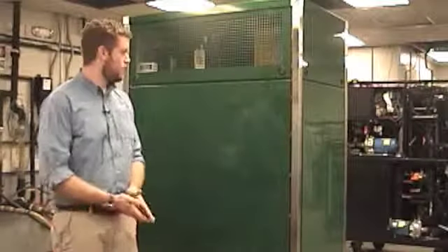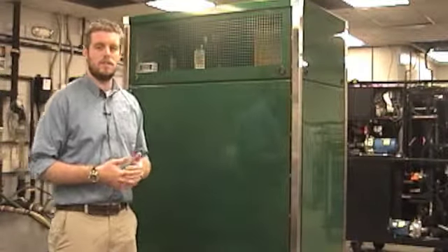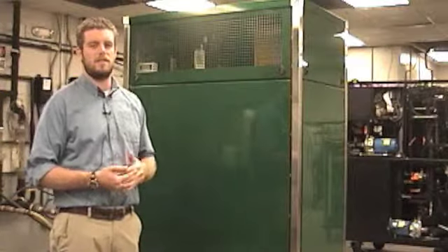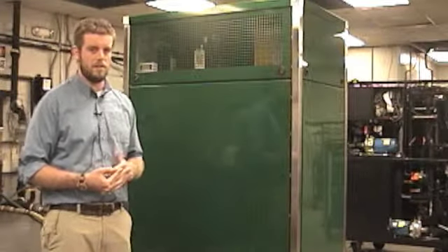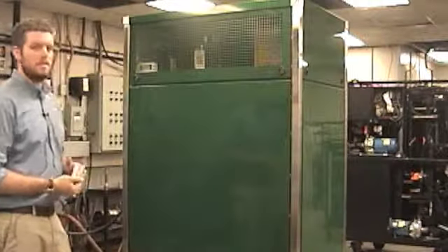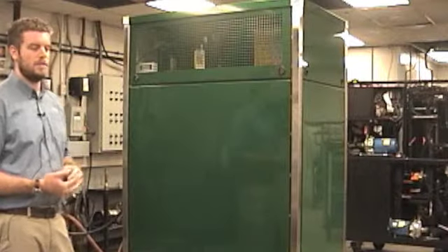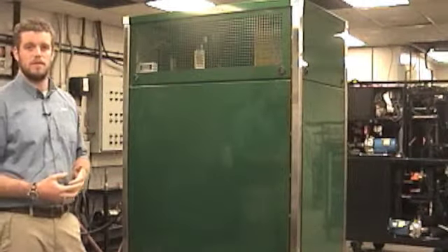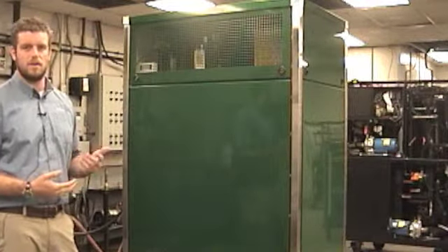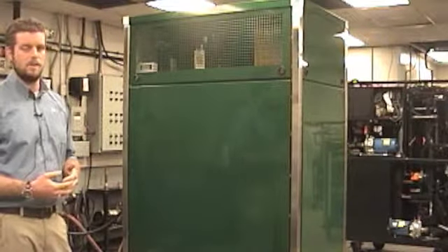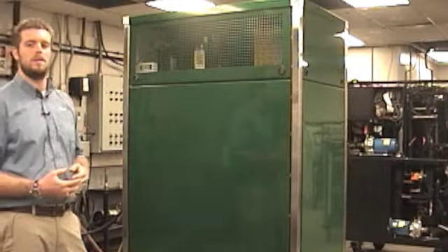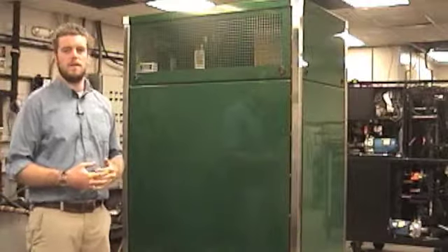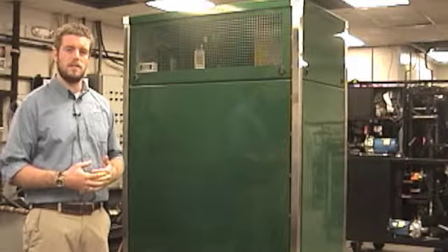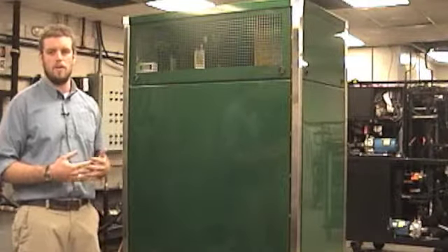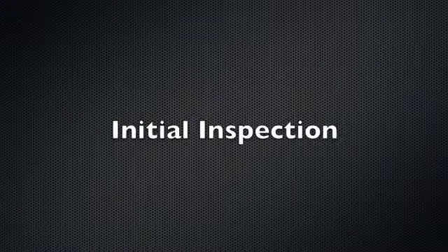Today we'll be reviewing the startup and installation of an ES60 RFCA drinking water chiller. Typically this unit would be hooked up to a building's drinking water system serving multiple outlets via a recirculating loop. Typical outlets would be drinking fountains, bottle filling stations, glass fillers on a sink, ice makers, anywhere that potable water is required.